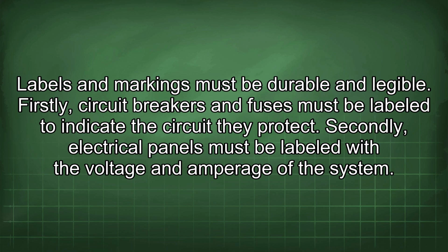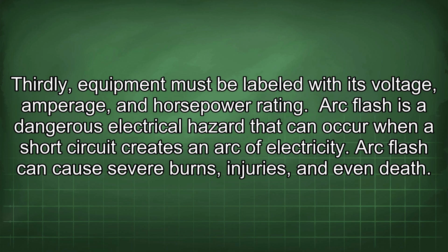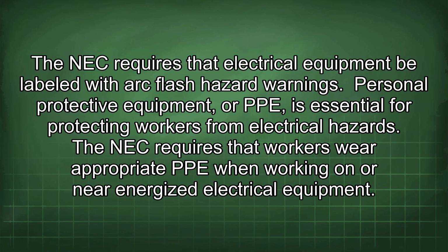Firstly, circuit breakers and fuses must be labeled to indicate the circuit they protect. Secondly, electrical panels must be labeled with the voltage and amperage of the system. Thirdly, equipment must be labeled with its voltage, amperage, and horsepower rating. Arc flash is a dangerous electrical hazard that can occur when a short circuit creates an arc of electricity. Arc flash can cause severe burns, injuries, and even death. The NEC requires that electrical equipment be labeled with arc flash hazard warnings.